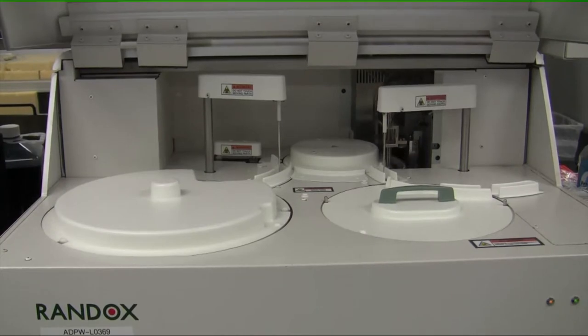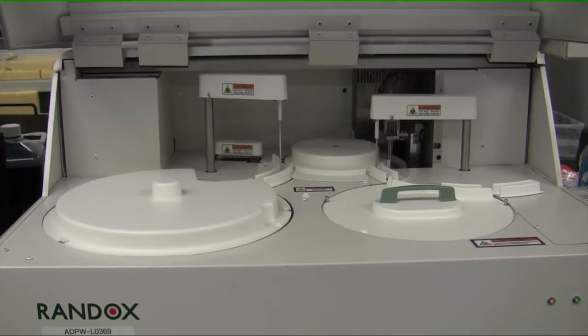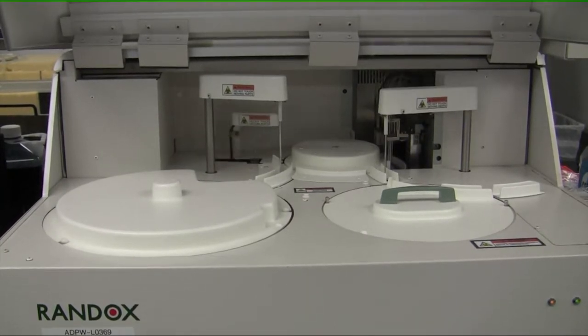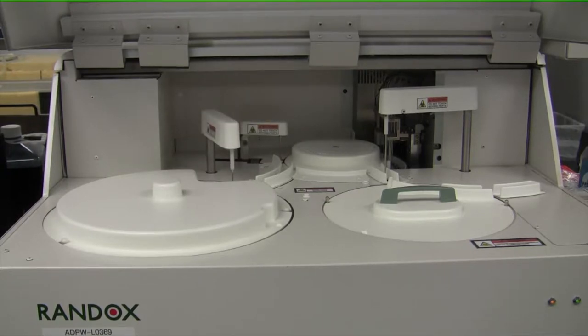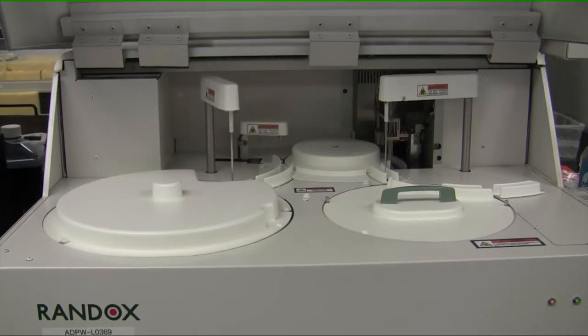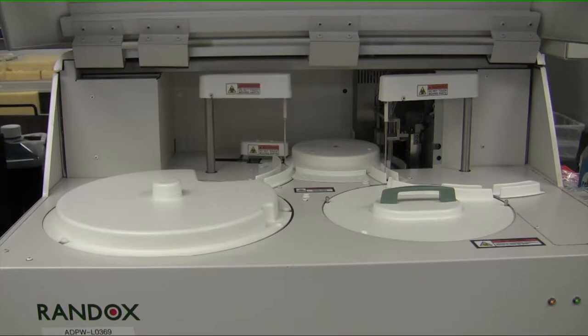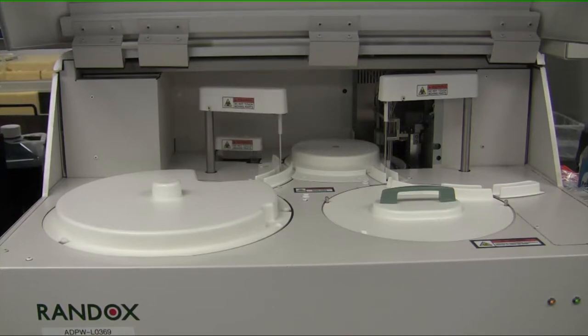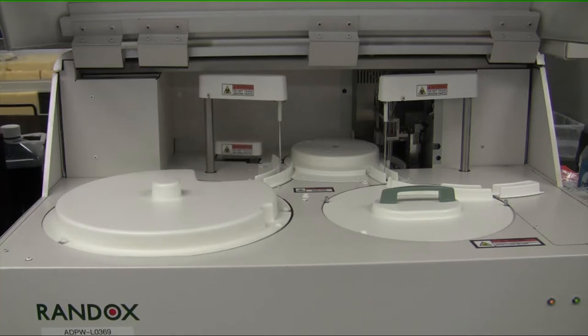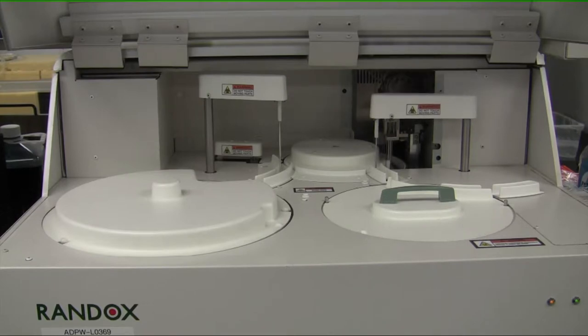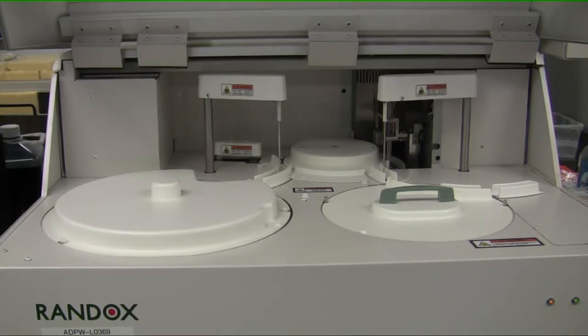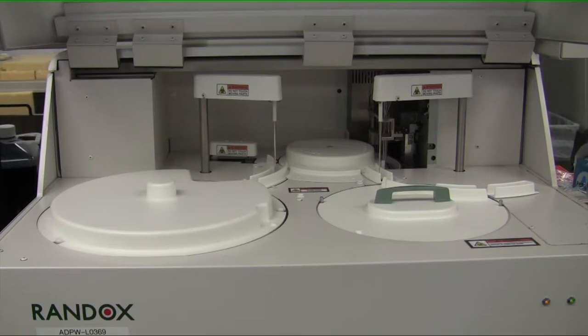So this is the instrument in operation mode. On the right-hand side, moving, you see that the sample pipetting arm is moving. On the left-hand side now, you see that the reagent pipetting arm is moving. So those two work together. The right arm pipetting sample into a cuvette, the left arm pipetting reagent into a cuvette. And then in the rear, there's a mixing paddle, which mixes the cuvette.